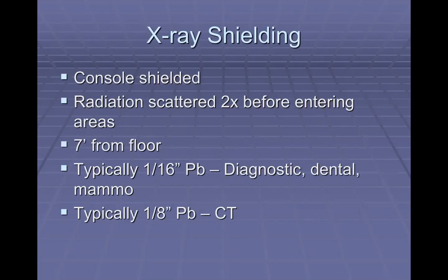So before we jump into Linacs and the real big machines, we'll just discuss basic general X-ray rooms, GenRad, mammo, dental X-rays. There are some basic requirements. These machines put out much lower intensity radiation. They put out much lower energy radiation. So a lot of times you can get away with just having the actual building materials themselves. They'll attenuate the beam enough to create a safe level.